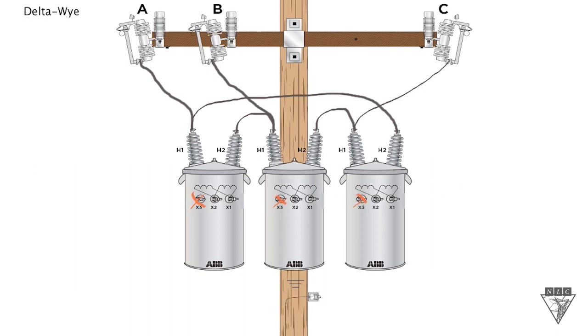Now we'll go ahead and do the connection. So the first thing we're going to do is tie our X2 bushings together. Now that they're tied together, we're going to run it down and take it to ground, and that's our secondary neutral connection. X2 bushings are all tied together, and then you run it down to your ground.